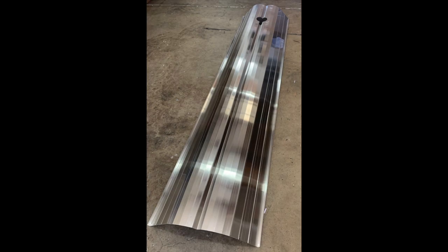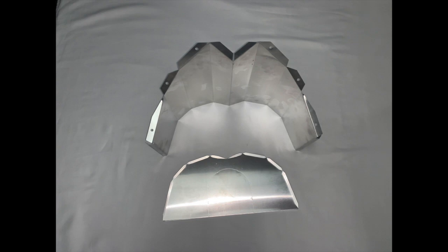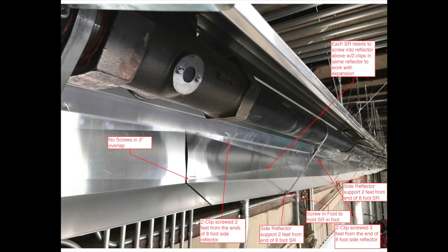When installing reflectors, they must alternate top and bottom. Using a C-clip vice grip on both sides of the reflector will ensure a straight run of reflector before you screw them, also using the support to keep them level. End caps are installed at the end of all open reflector ends. Joint pieces and end caps are used to make 90-degree turns with the reflector, and joint pieces are used for T's as well. Side reflectors are installed with 2 Z-clips and 2 side extension supports per reflector.